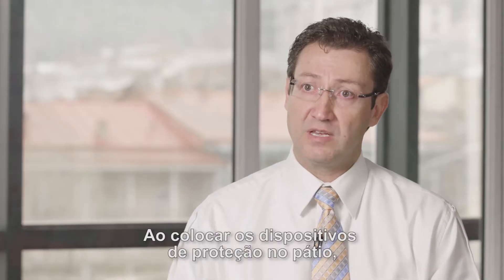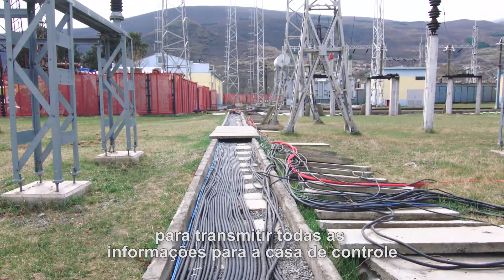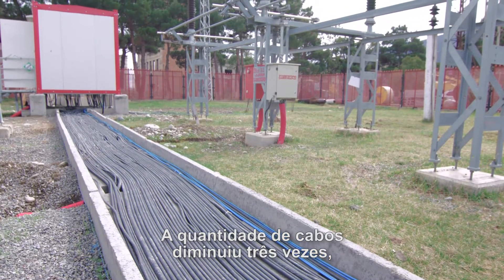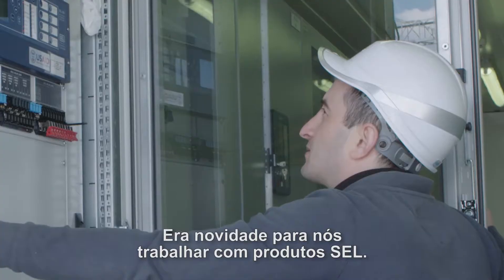By putting the protection devices out in the yard, the length of cable is short compared to what it would be to bring that information all the way to the control house. The quantity of cable has decreased three times, in some cases more. This was new for us to work with SEL products.